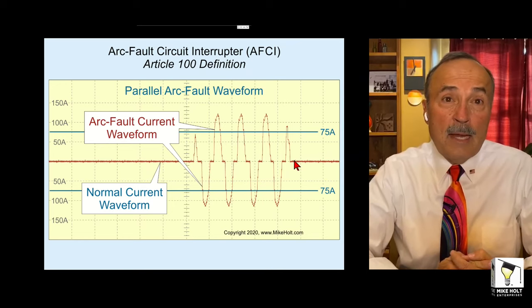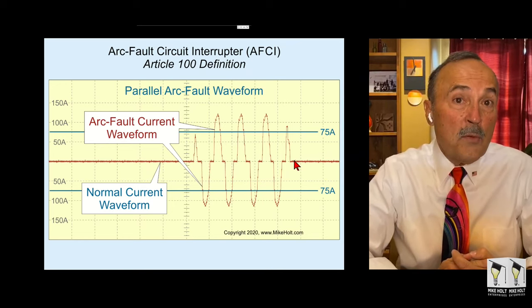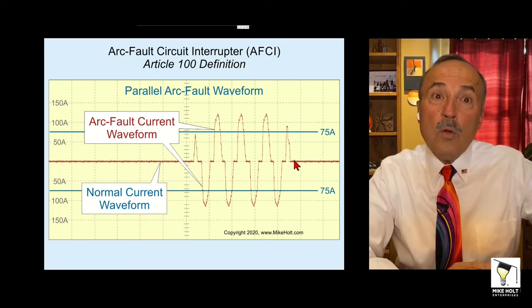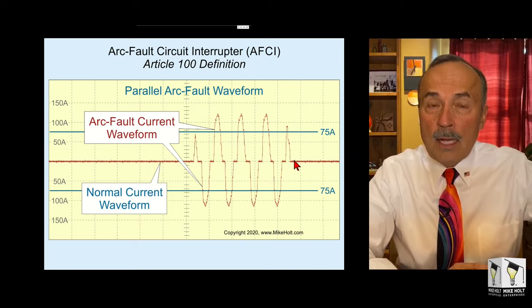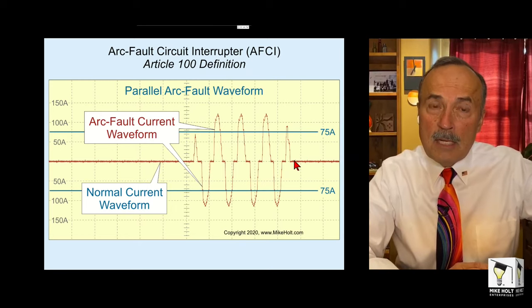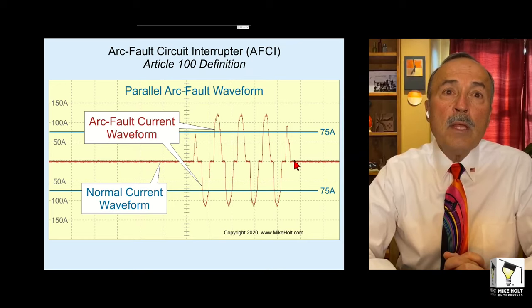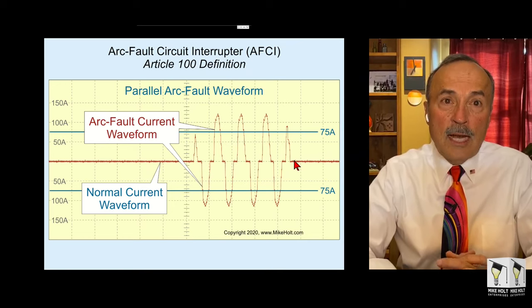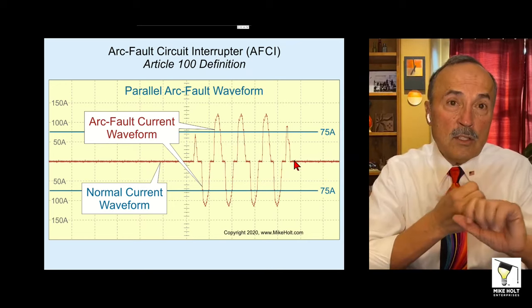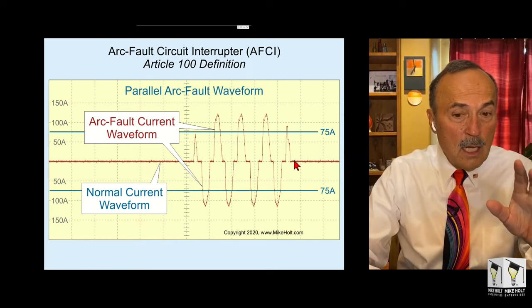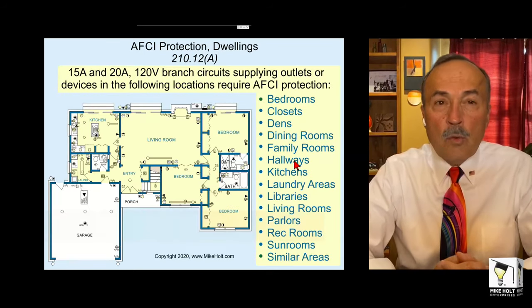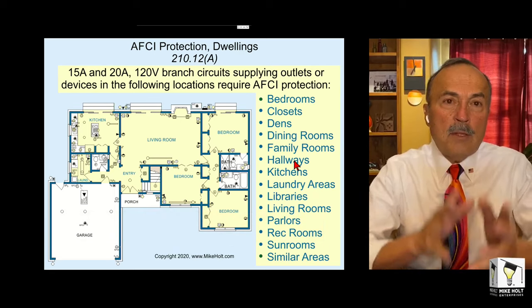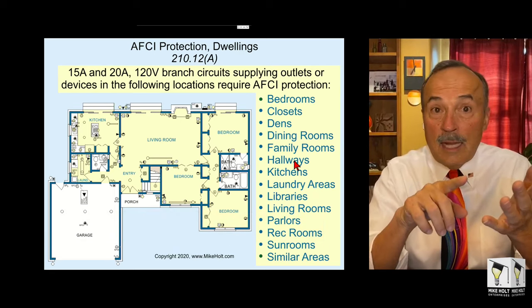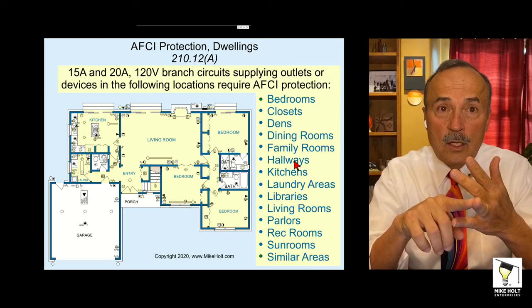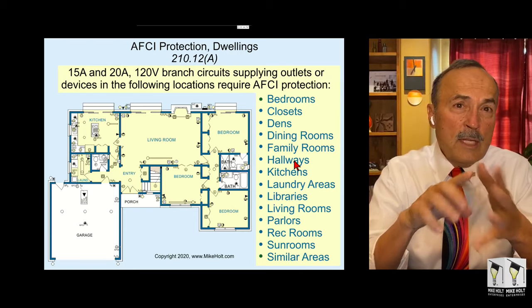Now, I don't know if anybody's actually selling any branch circuit feeder AFCIs, which was the old type that was only a parallel sensing device, but that's not permitted by the code. You need to have a combination AFCI, which detects both parallel and series arcing faults. All right, so that's the technology. So where is it required? Now, depending on whether you have the 2014 code, the 2011 code, the 2017 code, the 2020 code, you need to get to your code book.